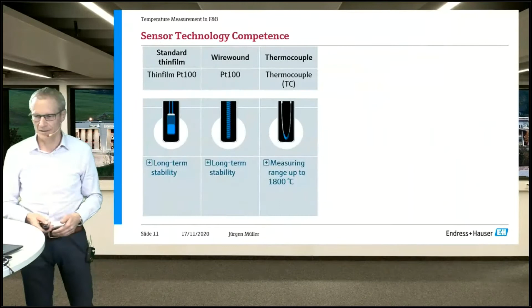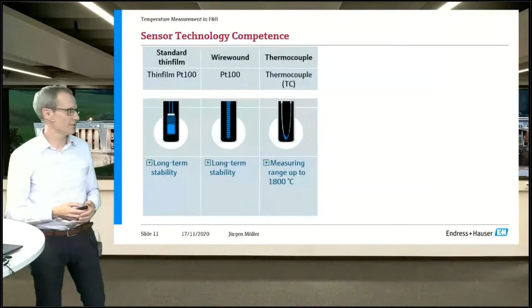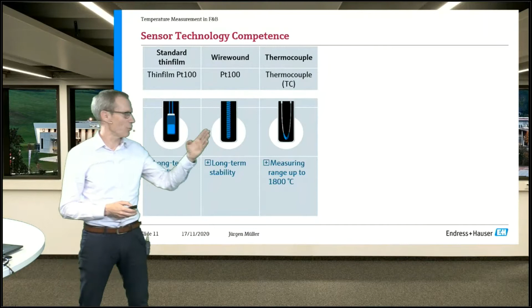Okay, looking at sensor technology, I want to mention three sensors: the standard thin film PT100, a wire wound PT100, and a thermocouple. The first two, standard thin film and wire wound, are PT100 sensors. PT stands for platinum, so the sensing element itself is more or less platinum, either as a thin layer or a wire wound around a ceramic bar.